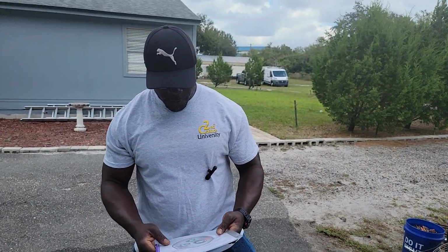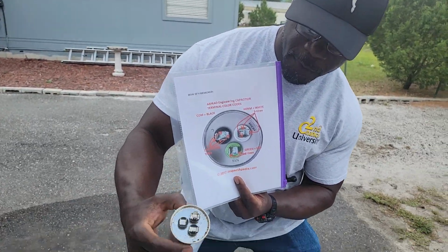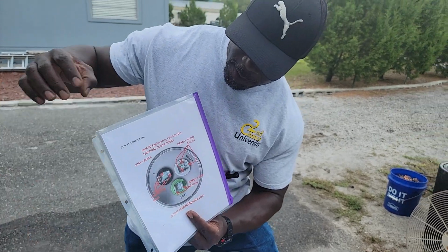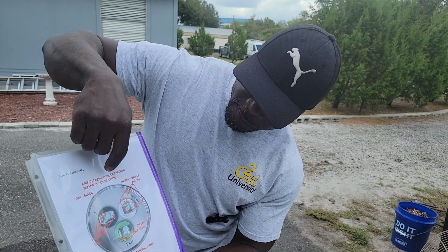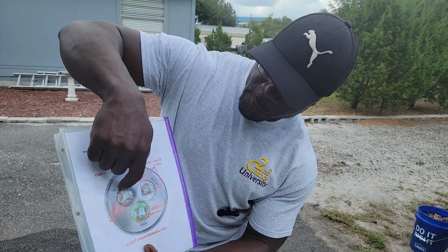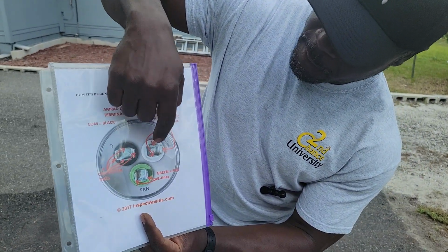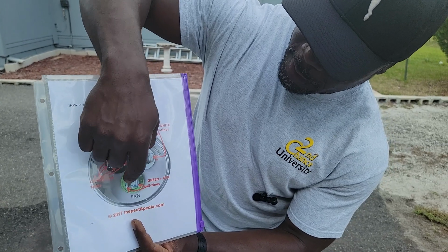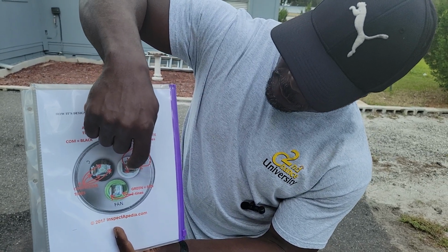Now, the key parts of the capacitor that you want to be aware of are on the top. Here you can see on the top, because we don't want to look at this small one right here, but we can circle back to that if you like, you have three sections. The first section is going to be your common, here with the black gasket around the bottom. Over here is going to be your Herm, and at the bottom is going to be your fan. Those small connections right there are called tines.